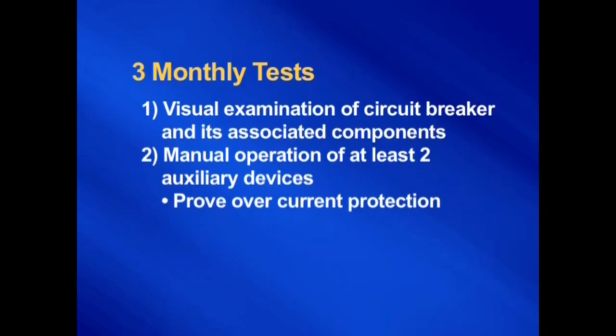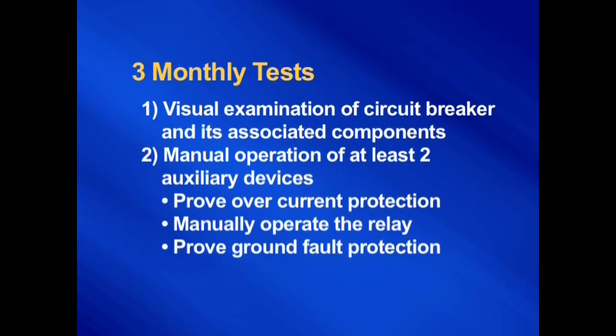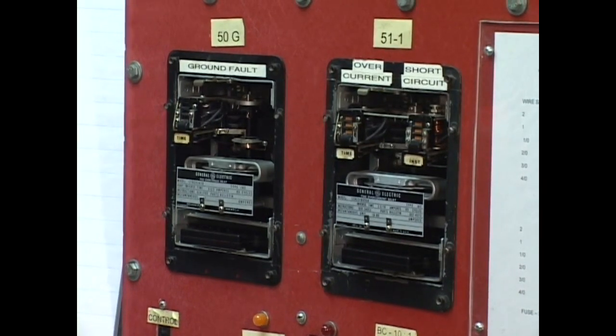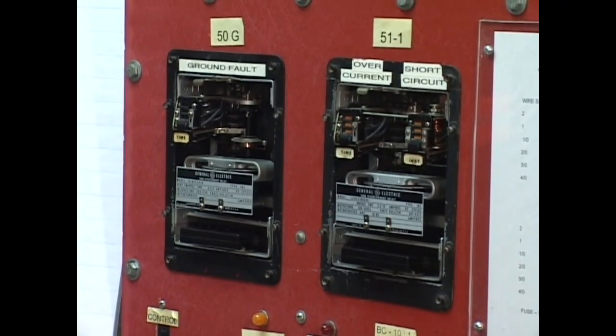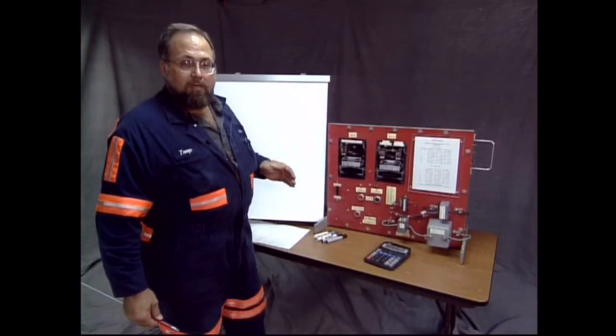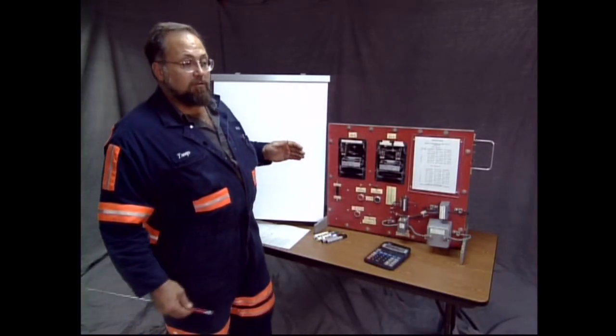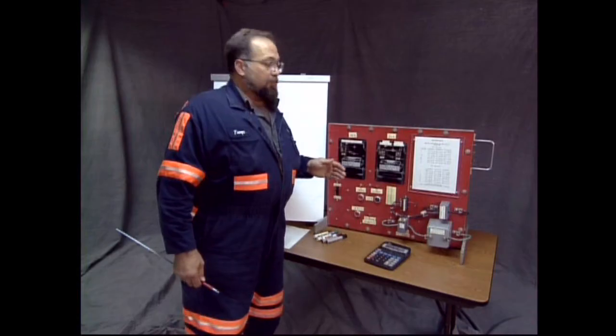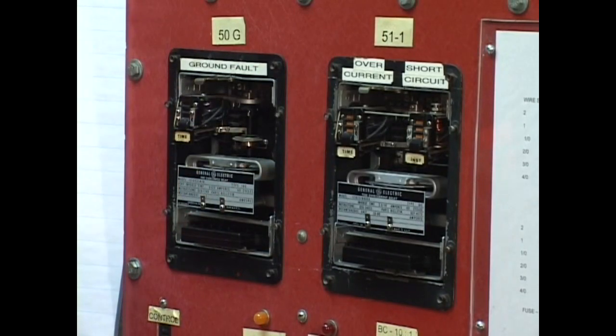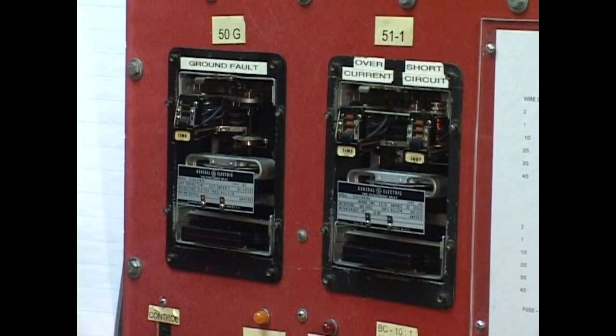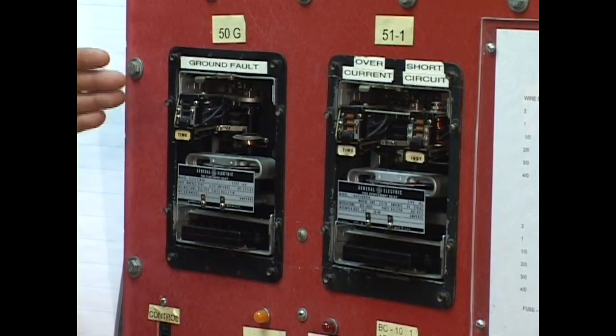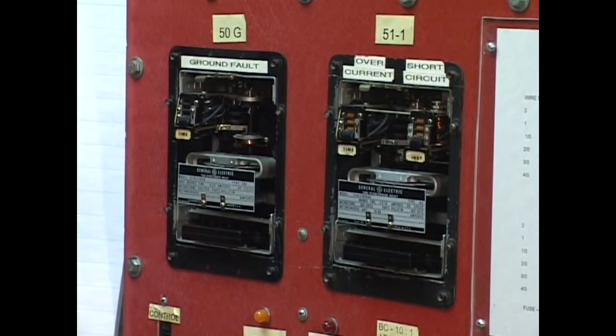You want to prove it has overcurrent protection. You want to manually operate the relay for overcurrent protection. And you want to prove that it has ground fault protection, that this ground fault relay will turn the breaker off. It will open the circuit breaker, turn the power off if you have a ground fault. And you want to manually operate this. You don't want to literally put a short circuit on your high voltage to prove this breaker works. You don't want to literally put a ground fault on it to prove that the breaker works.